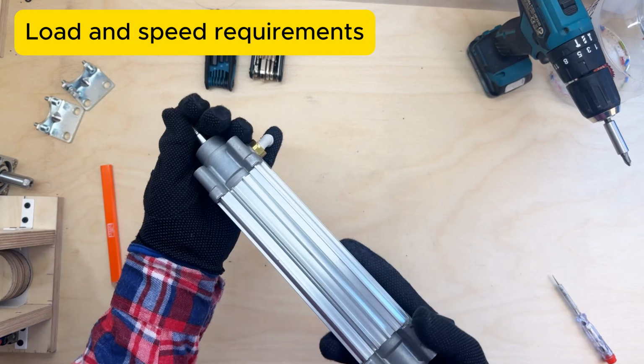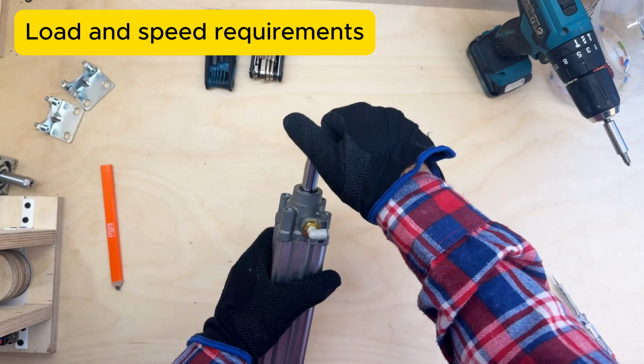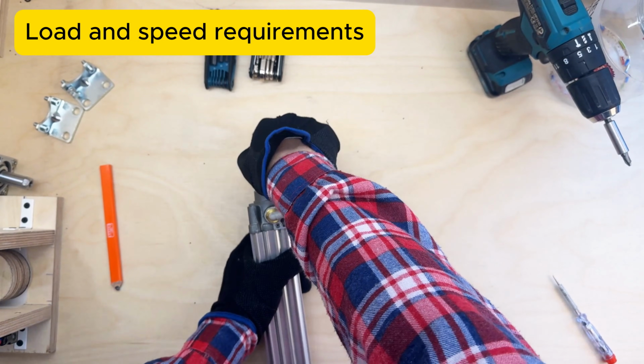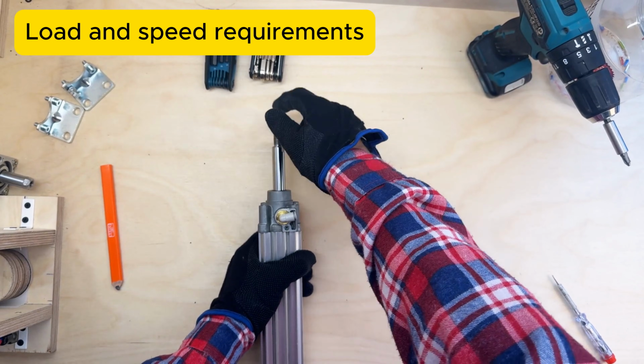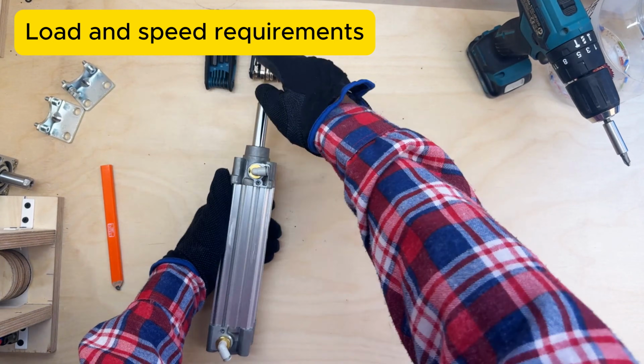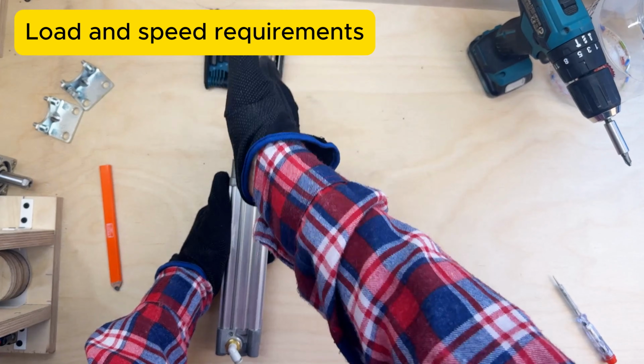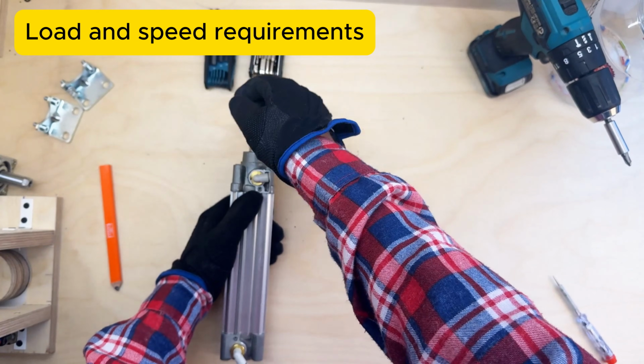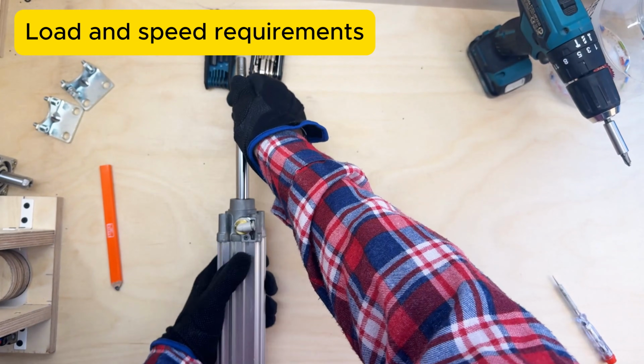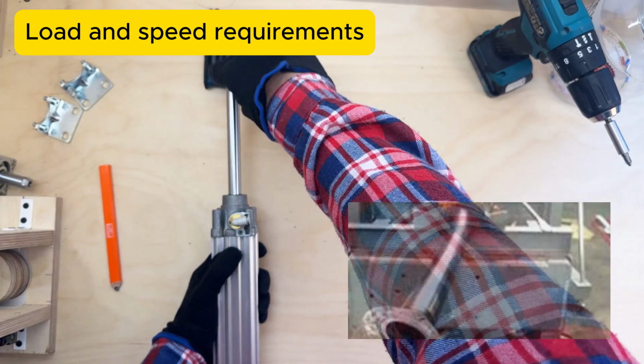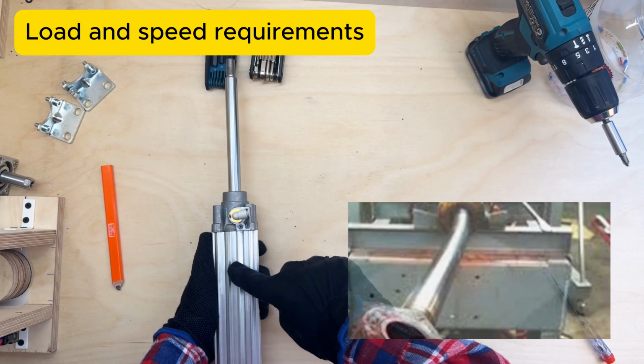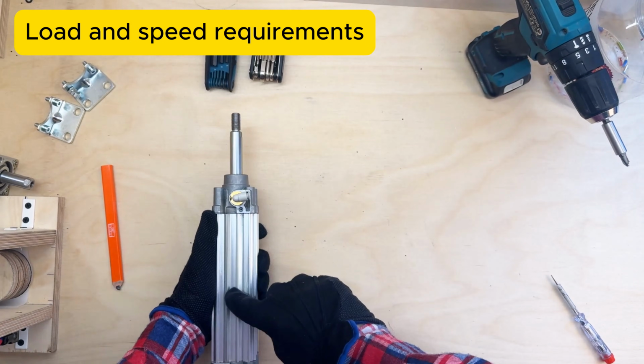Fourth thing is load and speed requirements. With load, I mean these dynamic forces that can apply from the side to the cylinder, because this type of cylinder takes very straight force, not at an angle. Because if it is at an angle, especially if the cylinder is extended, you have a big angle here, so you start to break this bore place.